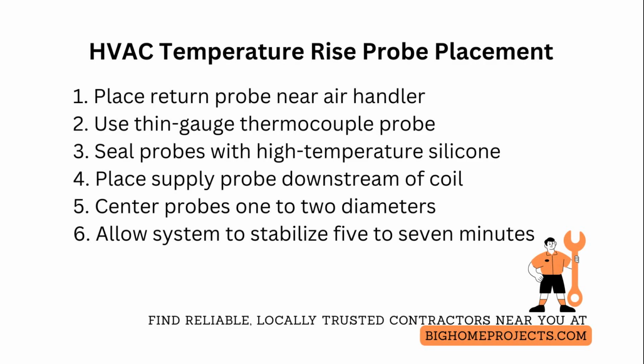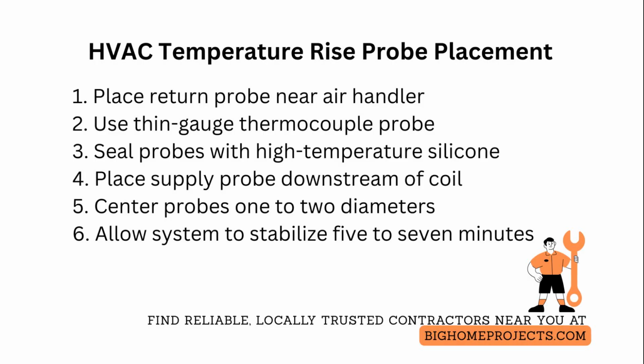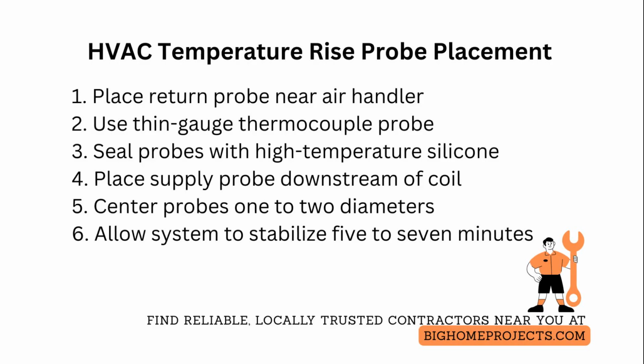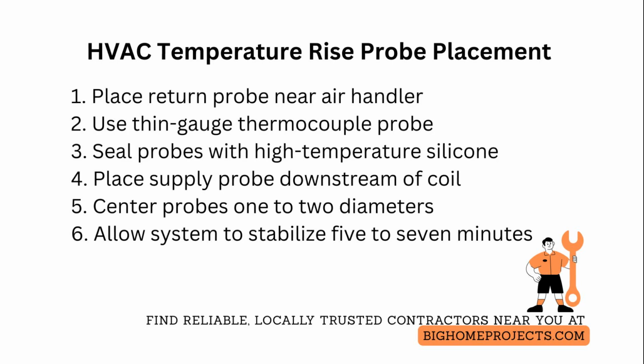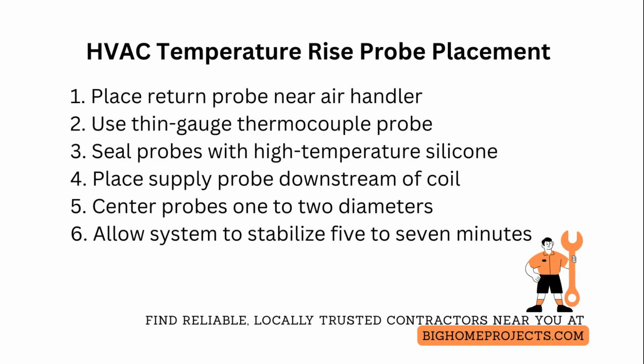For homes with low duct depth or rectangular ducts, average by measuring at 2 opposing points and use the mean. When using only one sensor per side, bias toward the center of flow. Always allow the system to stabilize for a minimum of 5 to 7 minutes after steady-state heat call before recording temperatures, and record multiple readings to confirm repeatability within 1/10 of a degree Celsius or about 2/10 of a degree Fahrenheit.